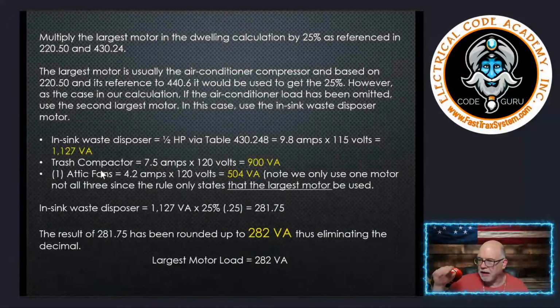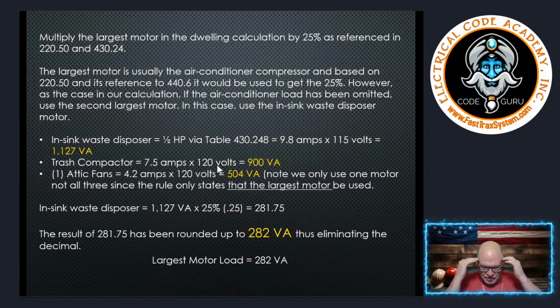All right, now, in our case, this is where you got to think. Remember when we did the AC, which is the largest motor in the building, that air conditioning compressor, right? But we compared AC versus heat, right? Well, guess what we did to that AC load? We got rid of it. We threw it away. We kept the heat. So we're not going to go after that air conditioning motor now. We have to now go for the next largest motor, right?